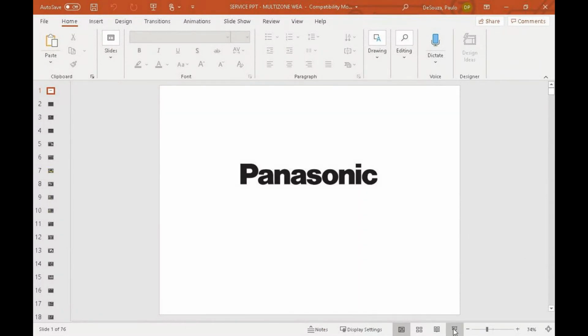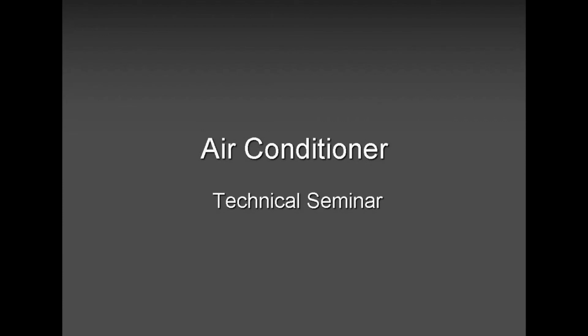Can any unit go below 60 degrees for heat mode? Below 60 degrees. Hold on, I have my calculator ready here, because we are talking Fahrenheit, right? Correct. Sorry, 60 degrees is 15 Celsius, anytime. 100% heating you will get. These units are meant to operate down to minus 15 single zone and minus 5 multi-zone Fahrenheit.